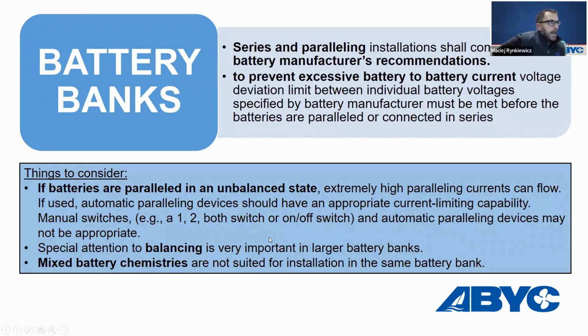Okay, so let's see, battery banks. Also, when you connect the lithium-ion batteries into banks, so when you create either parallel or series connections, follow the manufacturer's recommendations, because connecting the batteries can create currents or voltages that exceed the limits of the internal battery components. So often you have a battery manufacturer requirement that you cannot connect more than, let's say, 4 batteries in series. So just double check the instructions from the battery manufacturer before building a battery bank.